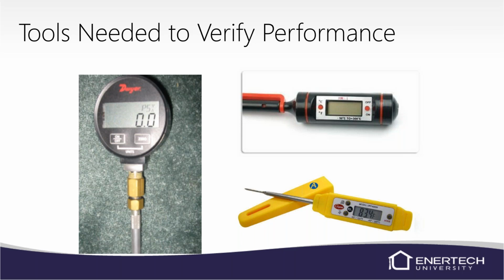I've got a couple of these, and I've used them. I've had them for about 4 or 5 years, and they're still intact. They've been pretty rugged. I let someone borrow one of them, and they did put channel locks on it and squished it. But other than that, it's worked out pretty well. I think this Cooper gauge or thermometer is like $20, so it's pretty reasonable. And again, it'll slide into those PT ports a lot easier for you. It does have a hold function, you can change it from Fahrenheit to Celsius, and it will also show your minimum and maximum temperatures that the thermometer has seen since you turned it on.